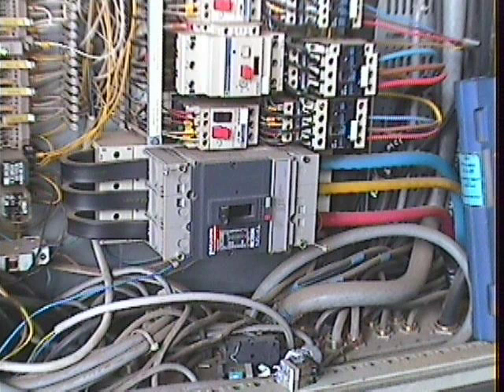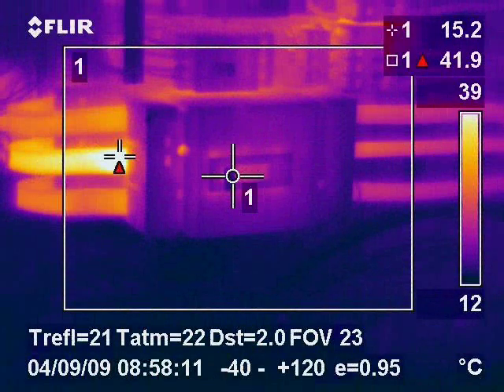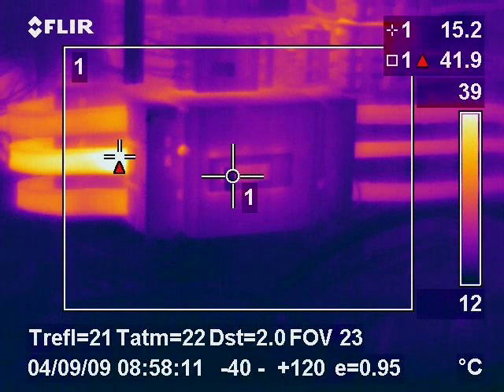Here we can see flexible bus bar connections feeding off a circuit breaker and feeding the rest of the panel. The thermal image found a loose connection, clearly visible in the thermal image but invisible to the naked eye.